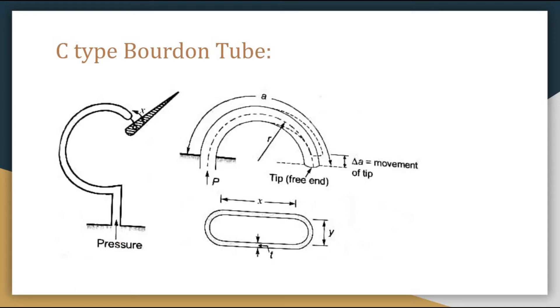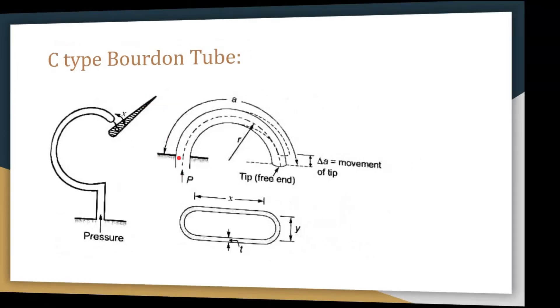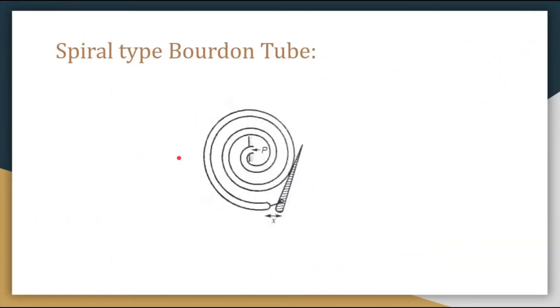The internal pressure tends to change the cross-section of the tube — it will bend in the direction shown by the arrow. The movement of the tip is ideally proportional to the pressure applied. As it bends, the tip moves along with it. Pressure is measured by inferring it in terms of displacement: as displacement increases, pressure also increases, and vice versa. This is the mechanism of the C-type Bourdon tube.